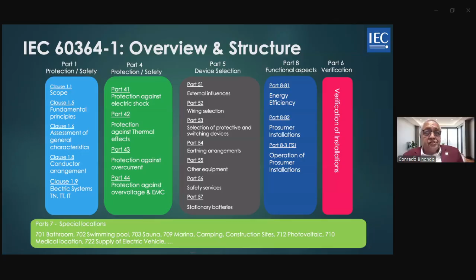Now, the introduction to IEC 60364-1 2025. As we know, this is the foundation - the parent document governing all low voltage electrical installation globally, up to 1,000 volts AC and 1,500 volts DC. Above this, we treat it in IEC as high voltage. So that's what we're talking about - medium voltage, extra low voltage. There are only two categories: low voltage and high voltage, because there is an installation rules for high voltage - it's a different standard. But as far as low voltage is concerned, IEC 60364 is for the low voltage installation.